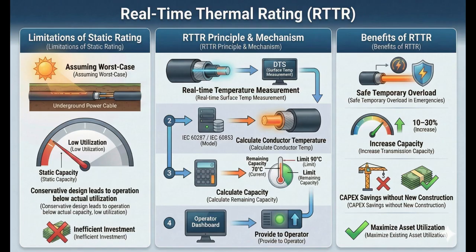RTTR goes beyond the limits of static ratings. Traditional ratings are conservative because they assume worst-case conditions, which prevents full utilization of assets. RTTR collects real-time cable surface temperature via DTS and uses internationally standardized thermal models to calculate conductor temperature and remaining capacity for operators. This enables safe temporary overload operation in emergencies and can increase transmission capacity by roughly 10 to 30%, depending on conditions.